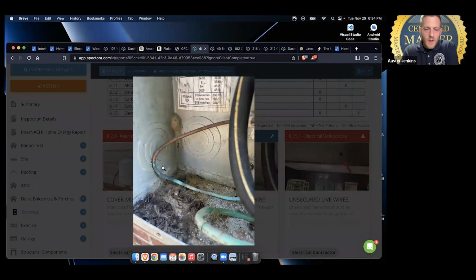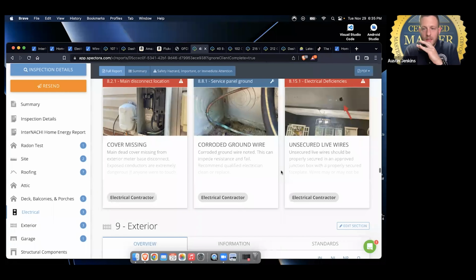You can see right here, which I thought was really cool, the corrosion starts right at the main point where the wire touches. If anybody remembers electrolysis, or galvanic action -- one of the two, they're really interchangeable, I can't recall the exact terminology -- that's taken over, and with gravity it has corroded that ground wire. You can see all the dead insects and bees and things like that. So I recommended that the ground wire be replaced.